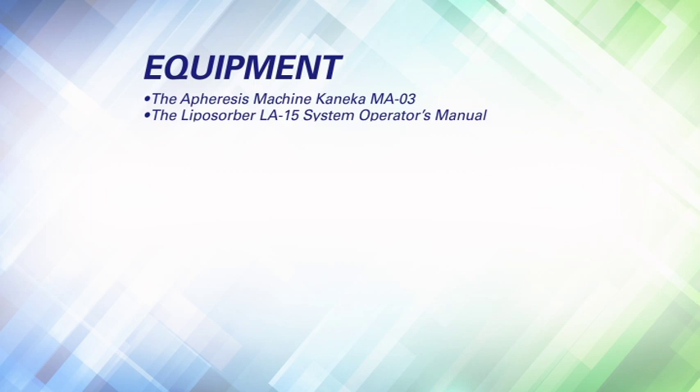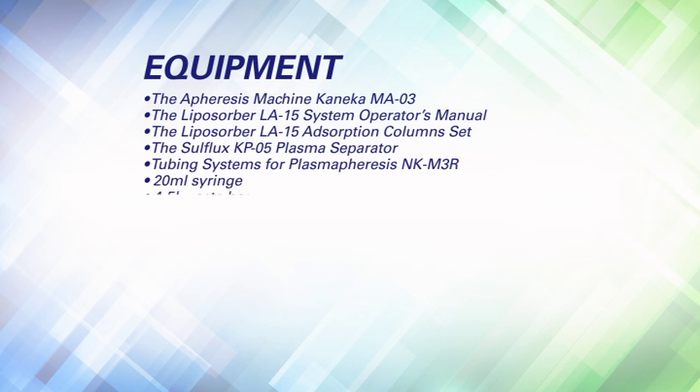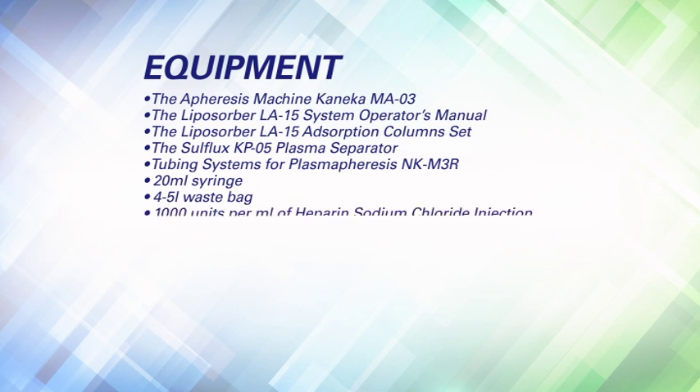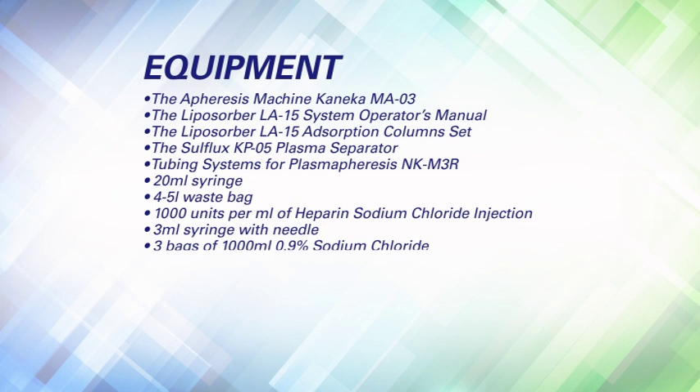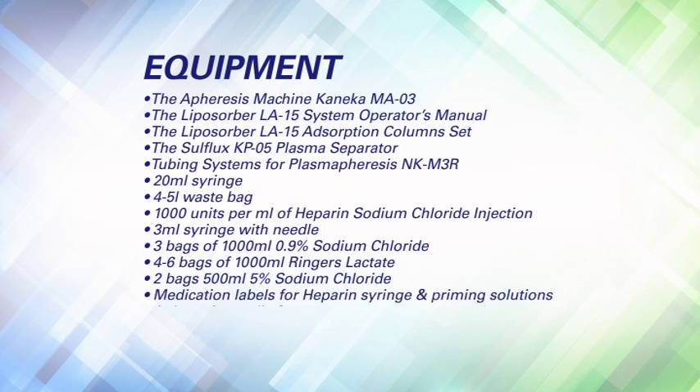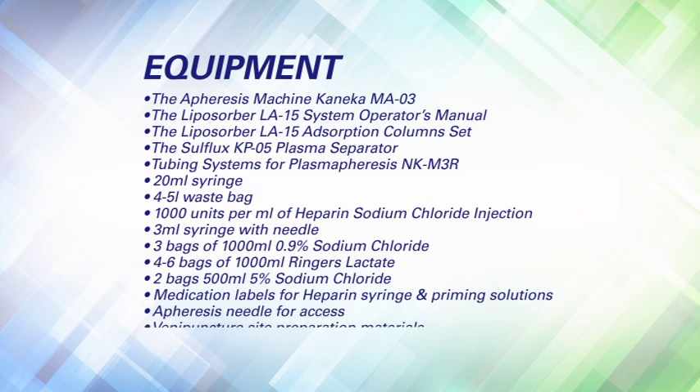Equipment. Before starting the training portion of this video, the following supplies and equipment are needed: the apheresis machine Kaneka MA-03, the Liposorber LA-15 system operator's manual, the Liposorber LA-15 adsorption column set, Sulflux KP05 plasma separator, tubing systems for plasma apheresis NKM3R, a 20 mL syringe, a 4–5 liter waste bag, 1,000 units/mL heparin sodium chloride injection vial, 3 mL syringe with needle, 3 bags of 1,000 mL 0.9% sodium chloride, 4 to 6 bags of 1,000 mL Ringer's Lactate, 2 bags of 500 mL 5% sodium chloride, medication labels for heparin syringe and priming solutions, apheresis needle for access, venipuncture site preparation materials, and plastic hemostat clamps.